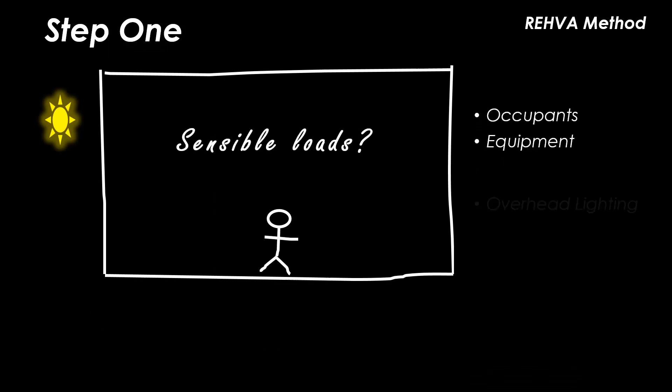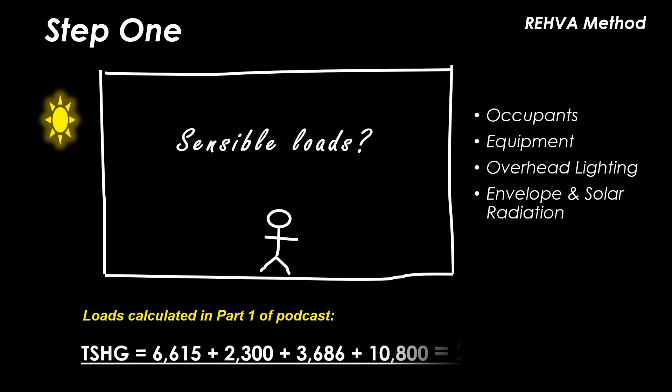The first step is to calculate the total space sensible heat load which will generally consist of occupants, equipment, lighting and envelope loads. To demonstrate the REHVA calculation method I will be using the same 900 square foot classroom used in part one of which the total sensible heat gains are 23,401 BTUs per hour.